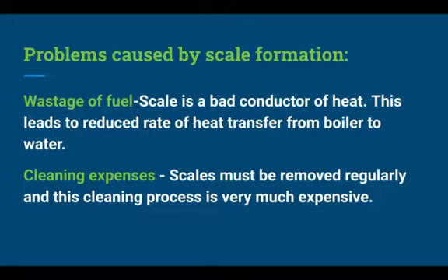First is wastage of fuel. The scale is a bad conductor of heat. Therefore, this leads to a reduced rate of heat transfer from boiler to water. So, in order to supply heat to water steadily, excessive overheating has to be done. And this causes an increase in fuel consumption. So, the presence of scales inside the boilers leads to more fuel consumption. That means there is a wastage of fuel.